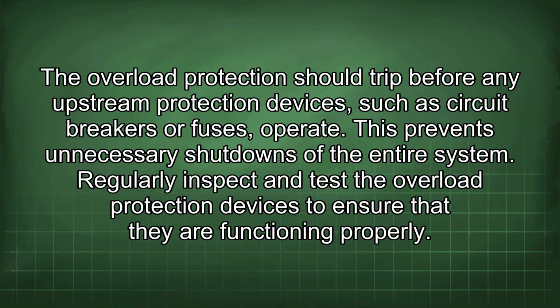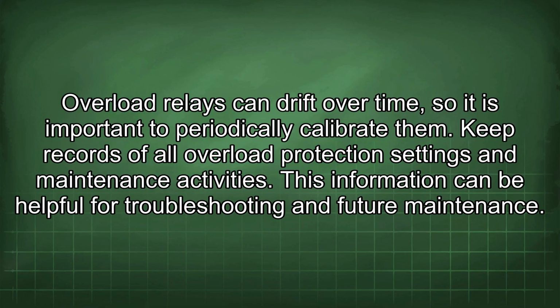Regularly inspect and test the overload protection devices to ensure that they are functioning properly. Overload relays can drift over time, so it is important to periodically calibrate them. Keep records of all overload protection settings and maintenance activities. This information can be helpful for troubleshooting and future maintenance.